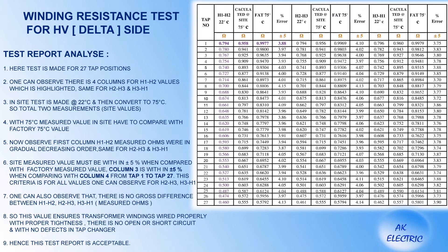Everything is within plus or minus 5 percent. One can also observe that there is no gross difference between H1-to-H2, H2-to-H3, and H3-to-H1. This ensures transformer windings are wired properly with proper tightness, there is no open or short circuit, and no defects in the tap changer. Hence this test report is acceptable.